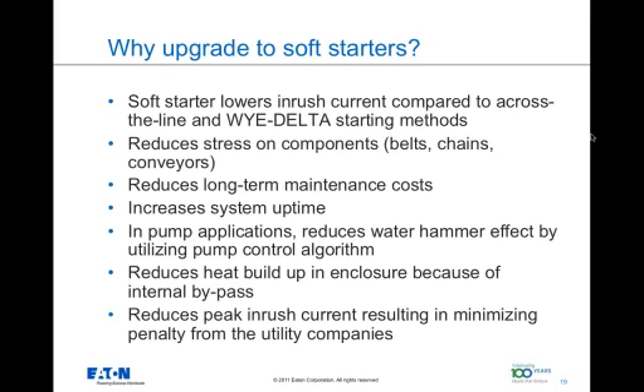The utility dictates that a facility should not be pulling more than a certain amount of current. Otherwise, it penalizes the customers till the customer proves that their demand has come down. Soft starters ensure that this requirement is met.